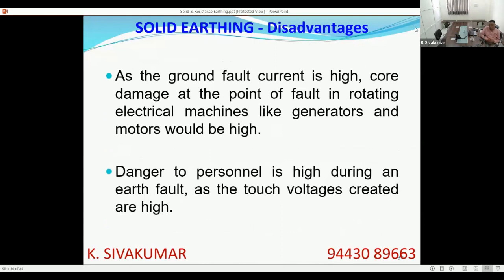And ground fault current is high if you have rotating machines. If you have rotating machines in your system and the fault happens within the rotating machine, core and windings are involved. If the core is involved, so generator and motor, if an earth fault happens inside the machine with solid earthing, high current will flow. So there are chances of core damage in the rotating machine. Similarly, when high fault current is there, the touch voltages are also very high. It is again grid resistance into the fault current. So if fault current is very high, the touch voltage hazard is also increased.